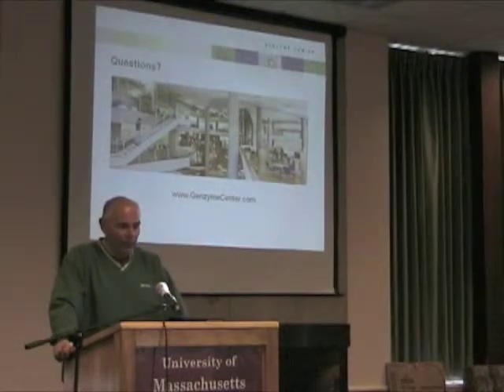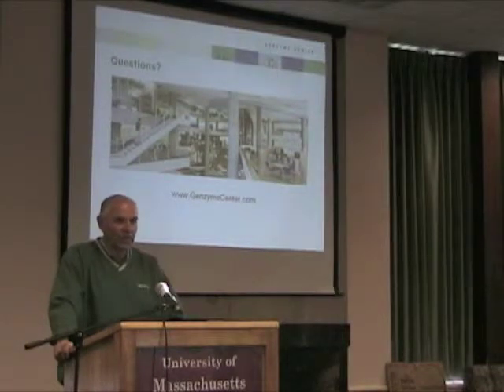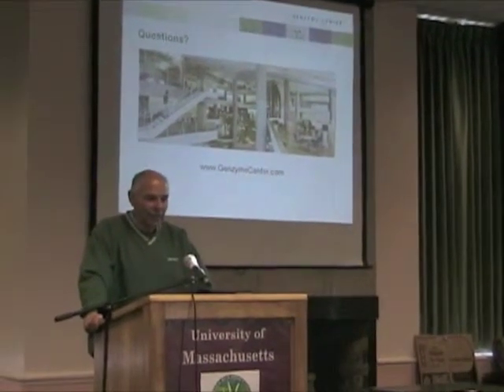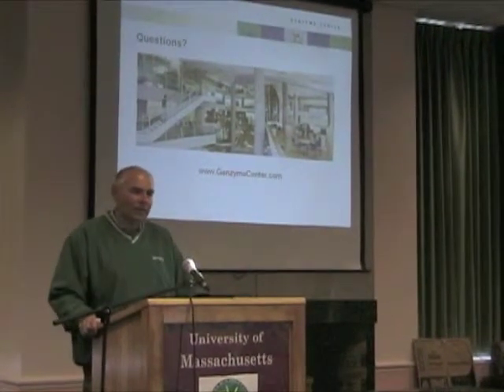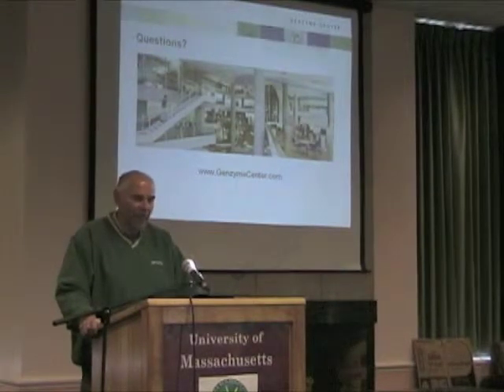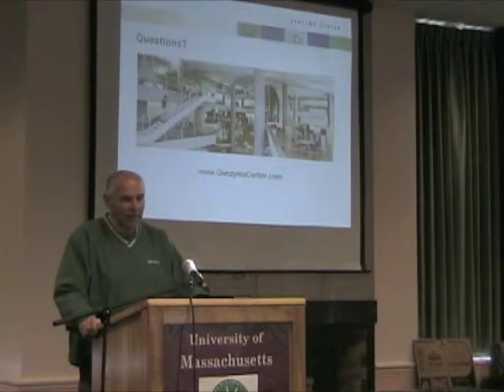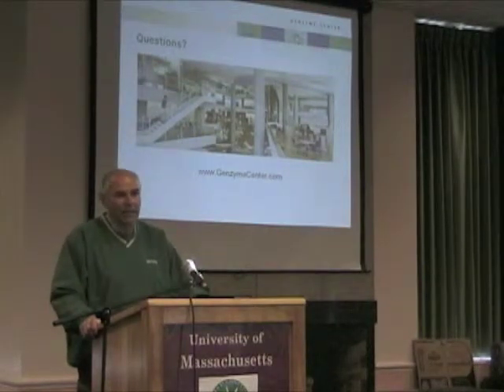The building right now is performing much better than it started out. We started out, it was designed for 2.0 watts per square foot. We have it down to 1.2, so we're able to save energy there. Water consumption, when they come out with that number, I still can't figure out how they figured that out, but we're saving on water, but not as much as that. I don't know where that figure came from. I've questioned the environmental people about that.